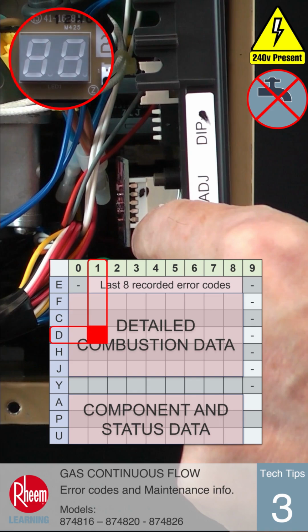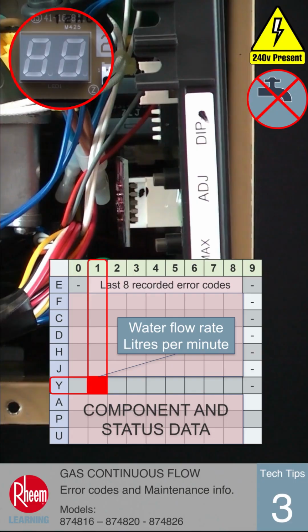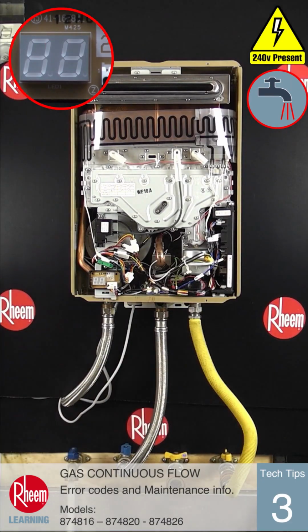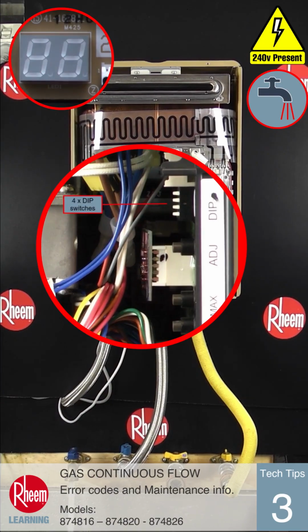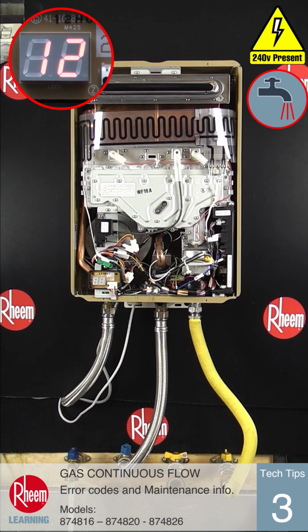Navigating to 1Y will show the live flow rate in litres per minute being recorded by the water turbine. This may be helpful to diagnose a faulty unit which is unresponsive when a tap is turned on to identify if there is a problem with the turbine not spinning. To hold the display at any grid location, turn on dip switch 2. The display will remain static for easier reading. To move on to a different location, turn off dip switch 2 to proceed.